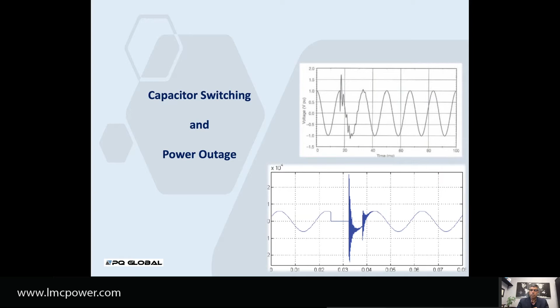A power outage—sometimes it's better for the power to just stay off. You see the sine wave going, and then all of a sudden it stops; at that point it's not a problem, the units went down, the power went out. But when it returns, it returns with a vengeance—a spike that can burn down the equipment. A lot of times people see their equipment damaged during power outages, but it's not the outage that damages it, it's the return of power that damages equipment if it's not well protected.